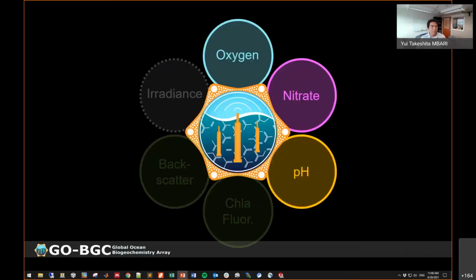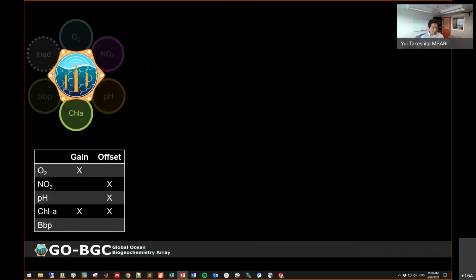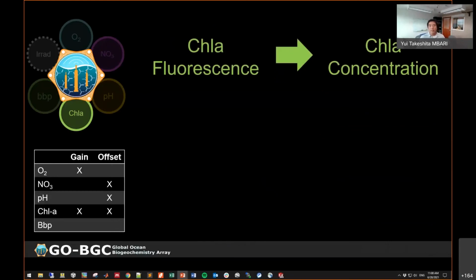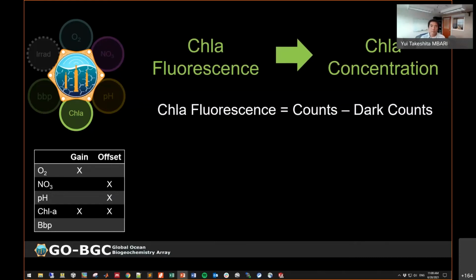Okay, I'm going to skip this slide. Okay, so going on to chlorophyll. Chlorophyll requires both a gain and an offset correction. The sensor measures fluorescence, and you need to go to concentration. The offset really only comes from when we measure the fluorescence.